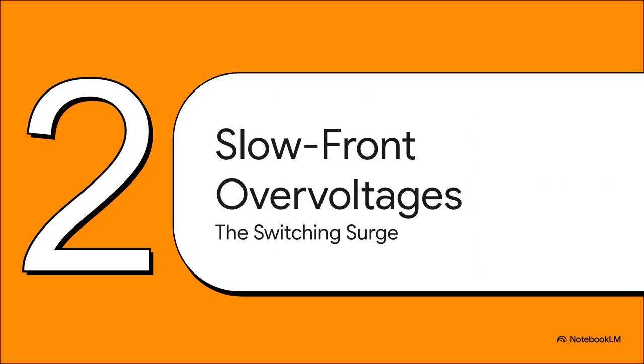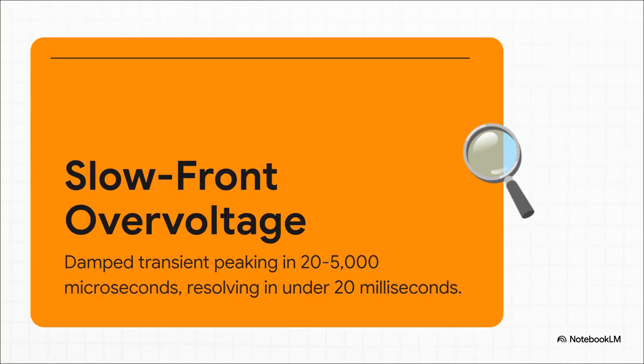Moving on to Section 2, slow front overvoltages, otherwise known as the switching surge. By definition, a slow front overvoltage takes anywhere between 20 and 5,000 microseconds to reach its peak. It's characterized by high amplitude, it can be unidirectional or highly oscillatory, and it features a highly damped wavelength. Once it hits that peak, the tail duration resolves in fewer than 20 milliseconds.